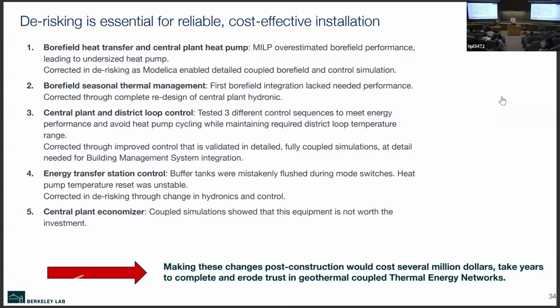Those literature values were just not applicable given the dynamic operation of the bore field and the small temperature differences in the reservoir loop. So in this de-risking step we corrected the design using the actual heat transfer rates that the geothermal model in Modelica reproduced, and reused that in MILP for one more iteration.